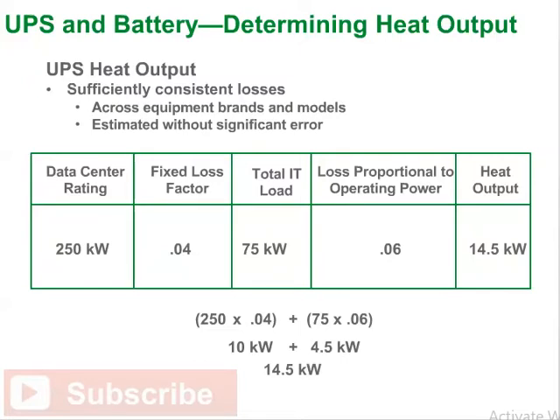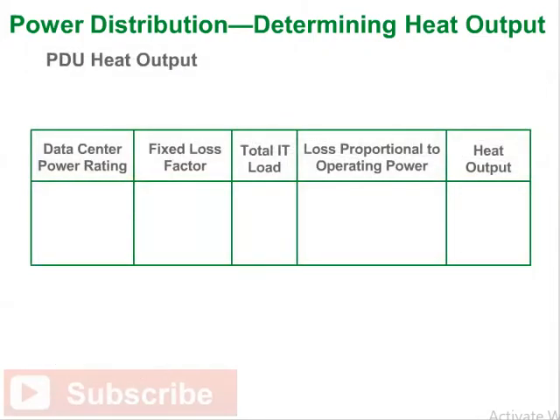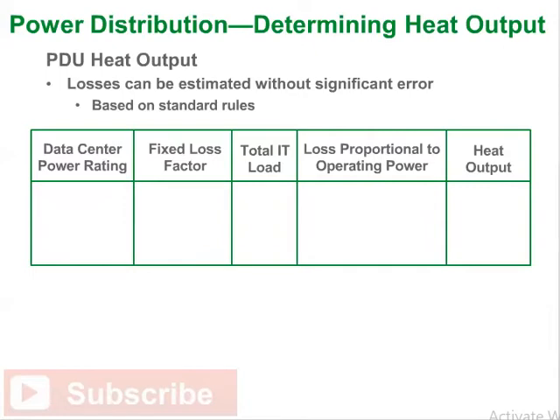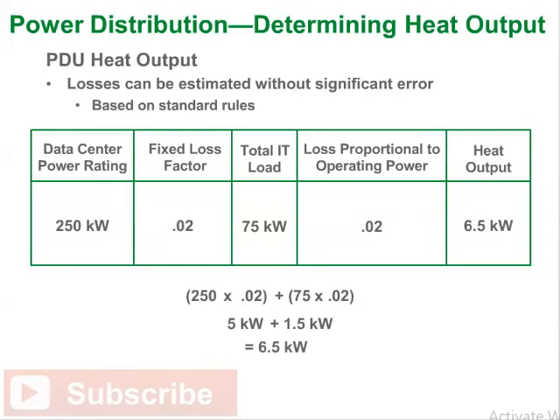Our next heat-producing component is the power distribution system. Like the UPS, it consists of a fixed loss and a loss proportional to operating power. We take the power rating of 250 kilowatts and multiply by the fixed loss factor of 0.02, giving 5 kilowatts. We then add this to 75 kilowatts multiplied by the proportional loss factor of 0.02, giving 1.5 kilowatts. The total, 5 plus 1.5, equals 6.5 kilowatts of heat from the power distribution system.